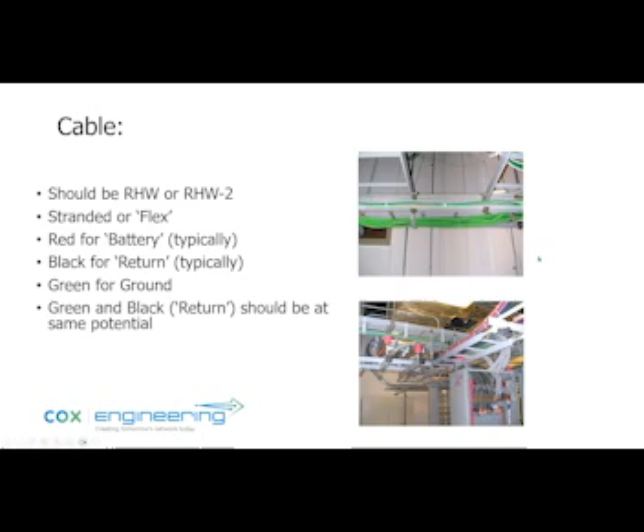Okay, now on the cable sizing, basically, you're going to look at what's the ampacity, and then you're going to use this table from the National Electrical Code. So, for example, we would typically use the 90 degree, but let's go ahead and use the 75 degree. So if you have a 65 amp load and you've got to size it to the breaker ultimately, then a number 6 cable is the size you're going to use. And if you have, say, 200 amps, you're going to use a 3/0, or really probably a 4/0 because 3/0 is not too common.